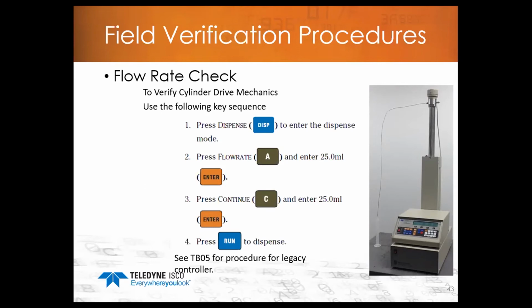So when we check the flow rate, we set it at 25 mils a minute, run it for 1 minute into a graduated cylinder, and record the collected volume. The flow rate should be within plus or minus 0.5%.